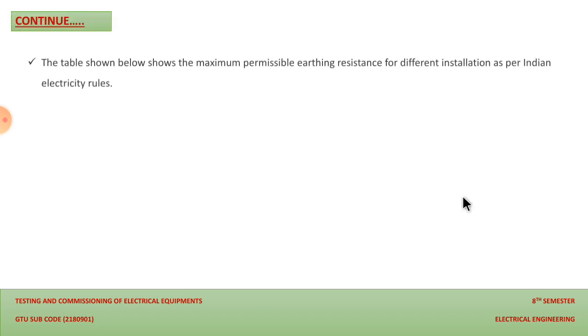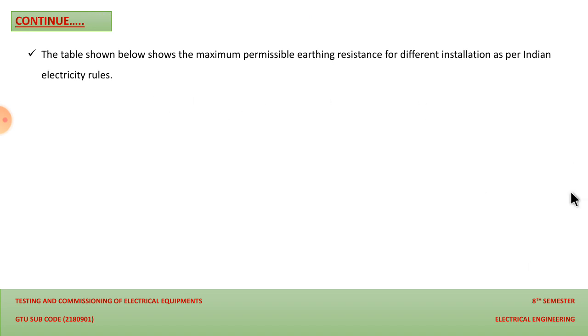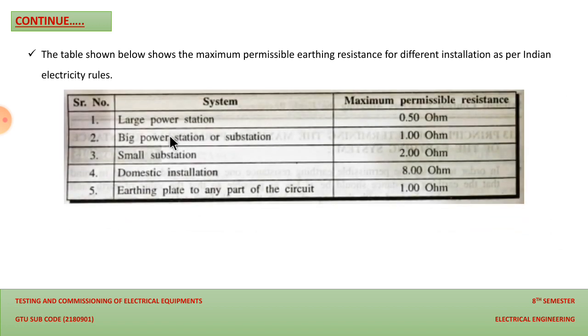So let us discuss these factors with the table. The table shown below gives the maximum permissible earthing resistance that we should keep for small and large systems, for different installations, as per the Indian Electricity Rules. According to these rules, we should keep the resistance of a particular area accordingly. Over here you can see that for a large power station, the maximum permissible resistance is 0.50 ohm. For a big power station or substation it is 1 ohm. For a small substation it is 2 ohm, for a domestic installation it is 8 ohms, and for the earthing plate to any part of the circuit it is 1 ohm.